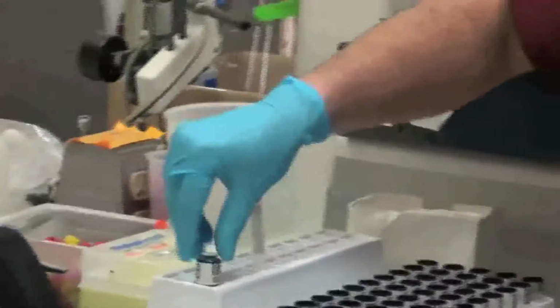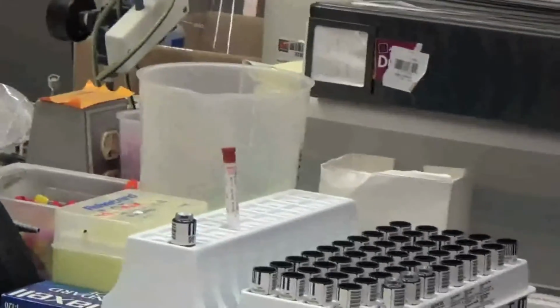It will have enough volume to go below, pull up its 10 microliters, and pull out without actually damaging the probe. The probe is sensitive to the surface tension of the fluid so that when it touches it, it knows, okay, just go a little bit beyond this and take my sample. If the sample were too low, the probe could actually crash into the sample cup, and then it would get off kilter and out of alignment, and we'd have a problem.